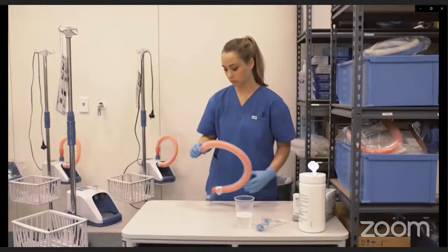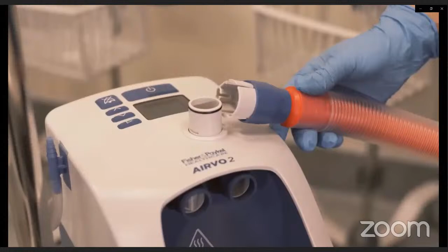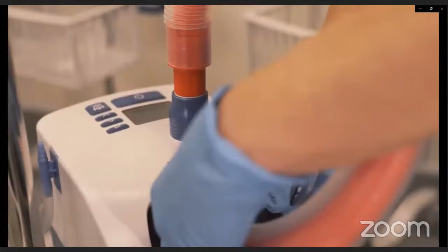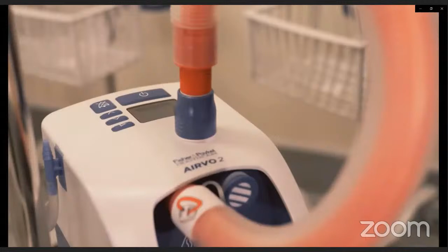First, connect the red disinfection tube to the AIRVO 2. One end of the disinfection tube has a blue plastic connector. Lift the sleeve and slide the connector onto the unit. Push the sleeve down to lock. Connect the red end of the disinfection tube to the left-hand chamber port and push fully into position. Then fix the blue filter cap securely onto the right chamber port. The AIRVO 2 is ready for disinfection.